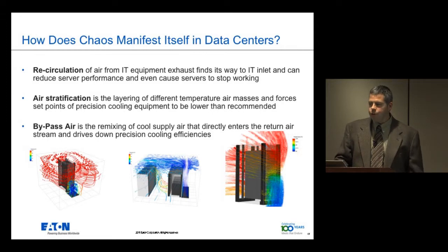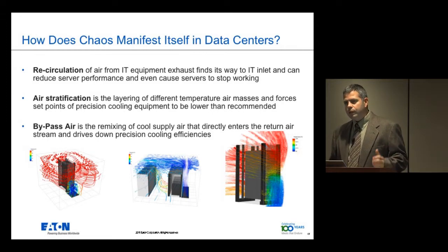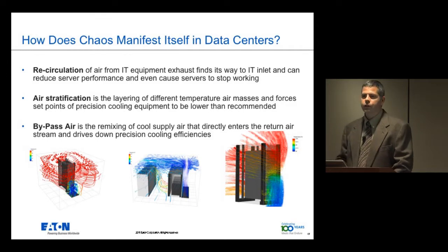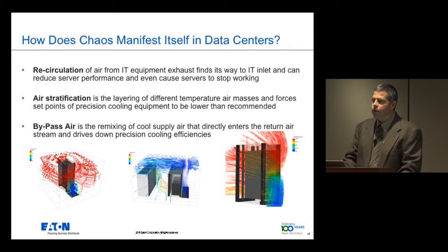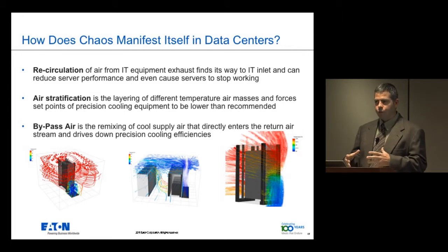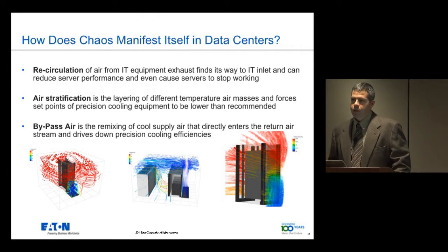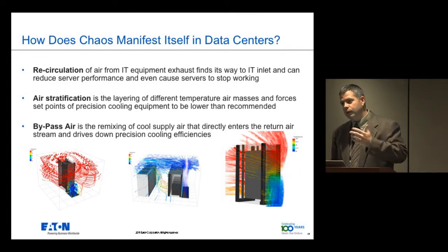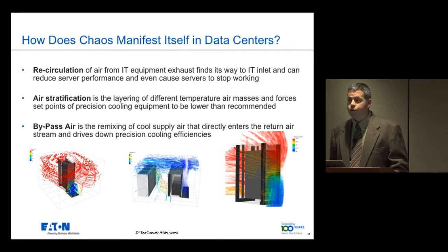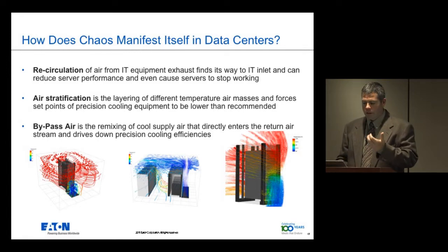Then there's bypass. It has a little bit to do with what we talked about in rack hygiene, but it's basically when you have the hot air mixing in directly with the cold air stream. Sometimes, in order to fight that, people will change the set points or the fan power on their CRAC units, which will pump more cold air under the floor. But as a result, the velocity of the air coming out from the floor tile, especially if the floor tile doesn't have enough open space, will shoot the air up faster, and sometimes that will just bypass the rack altogether and shoot right back to the CRAC unit. And then the CRAC unit thinks the room is much colder than it really is, or at least colder than what the servers are seeing, because the velocity is just too fast. So the cold air is not able to stop and go into the servers.